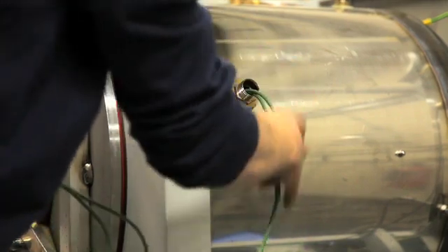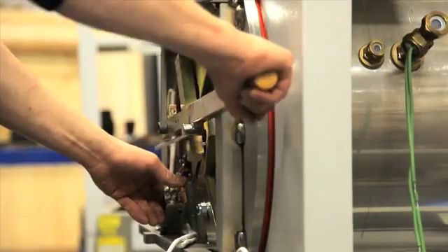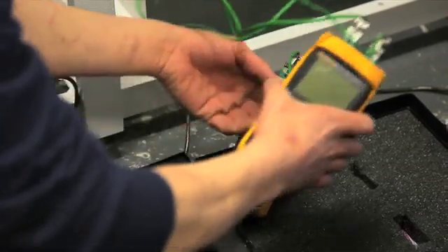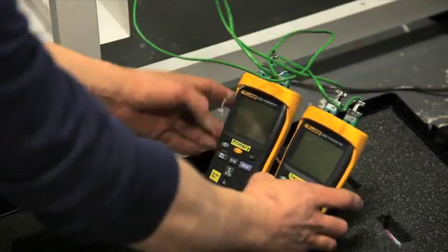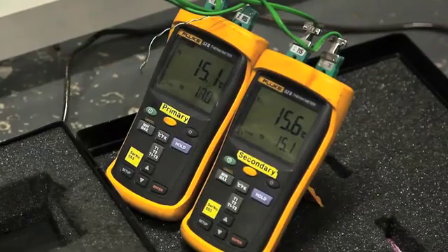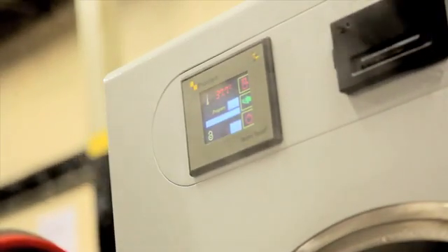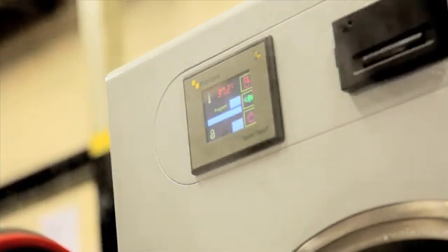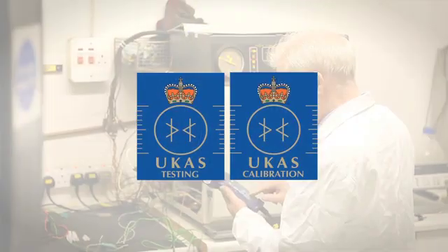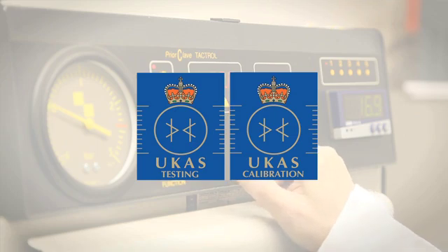To ensure an autoclave achieves the desired operating temperature, the PriorClave calibration service provides accurate adjustment of the control system. Calibrated thermocouples are connected next to the temperature control probe and monitoring probes of your autoclave, and these will be coupled to a traceably calibrated digital thermometer. Recorded readings are checked against those shown on the temperature controller and ancillary equipment, and any adjustments made. The accuracy of the test equipment is guaranteed as PriorClave operates a UKAS calibration laboratory.